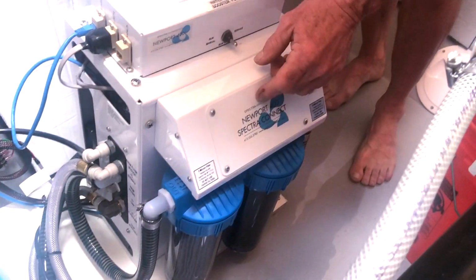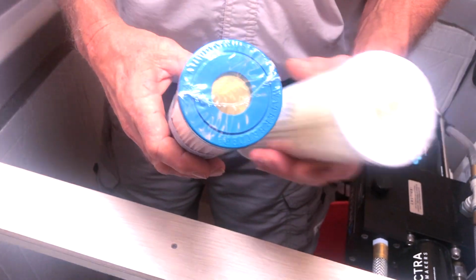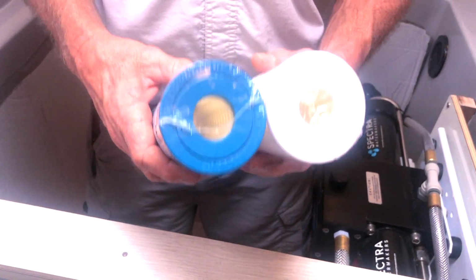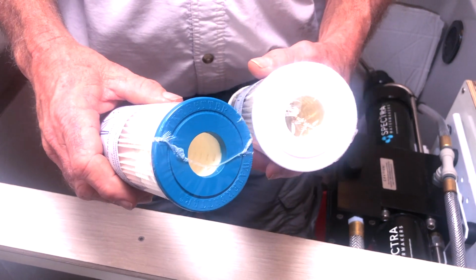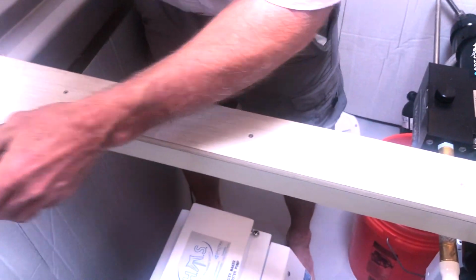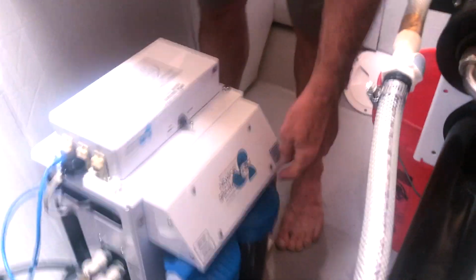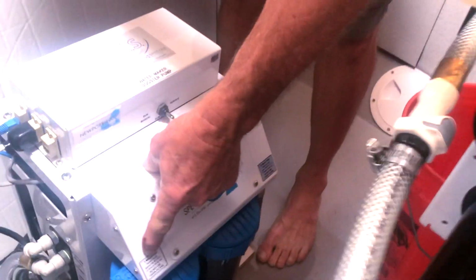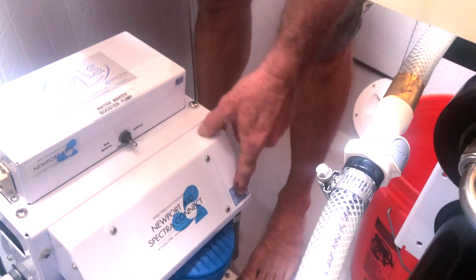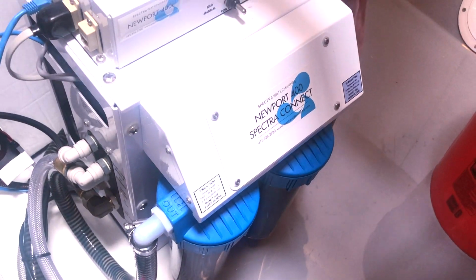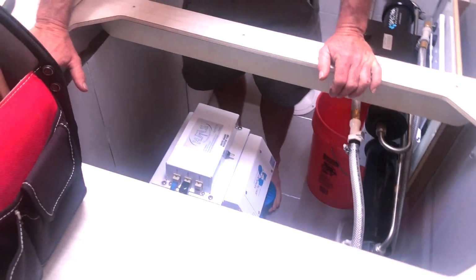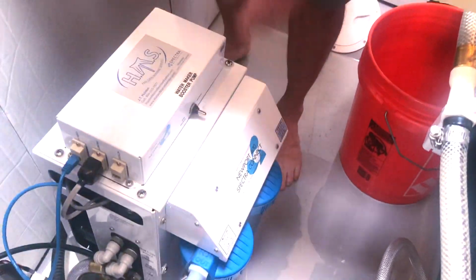And the filters themselves, here's the filters. Other than my name being on it, it doesn't have any markings as far as numbers, which one's 5 and which one's 20. So they're color coded. White is 5 and blue is 20. And you can see right on the top, we got these two stickers. The 5 micron sticker says 5 micron and it's white. 20 micron is blue, so you don't mix them up. If you mix them up, you throw the sensors off a little bit, and she'd probably shut down and say service pre-filters. So anyways, that's coming up from the boost pump to your first 20 to your 5. This is all salt water.